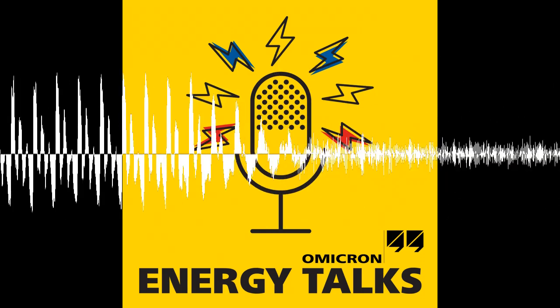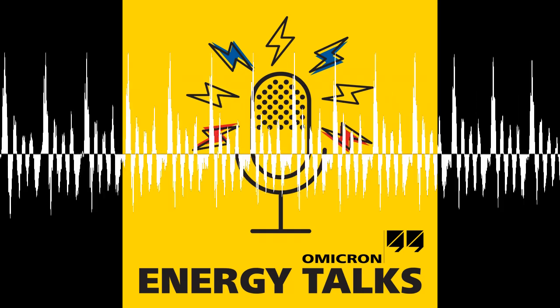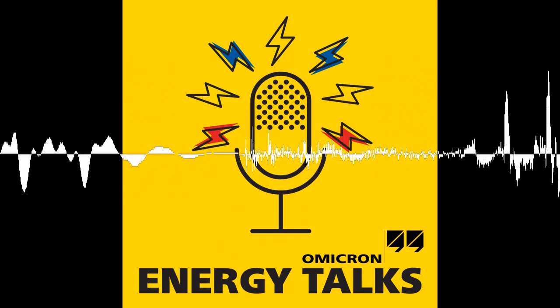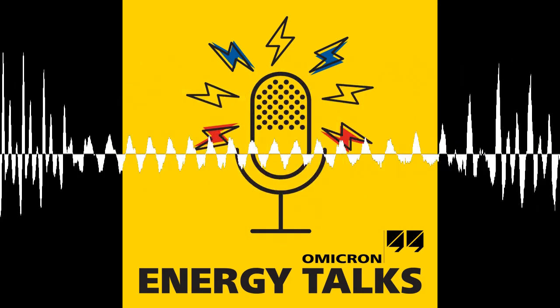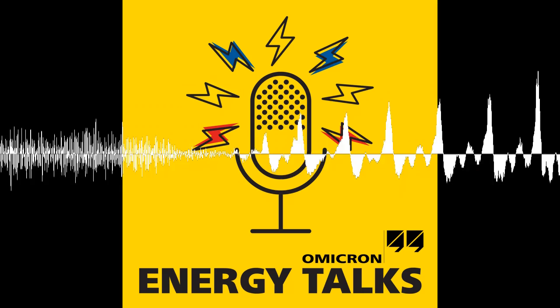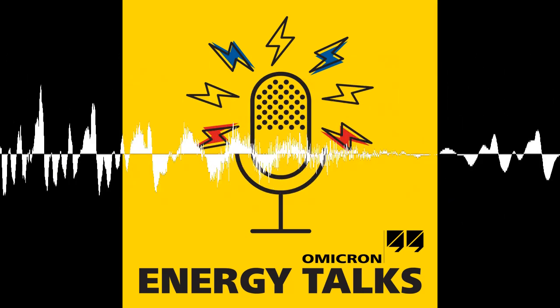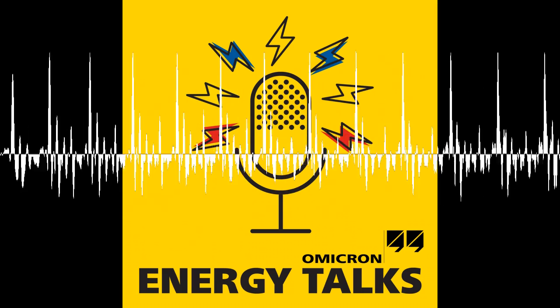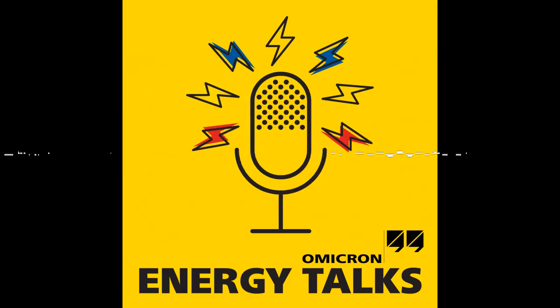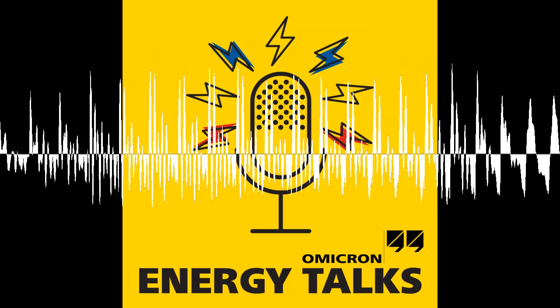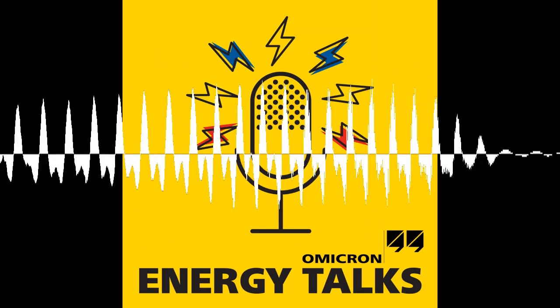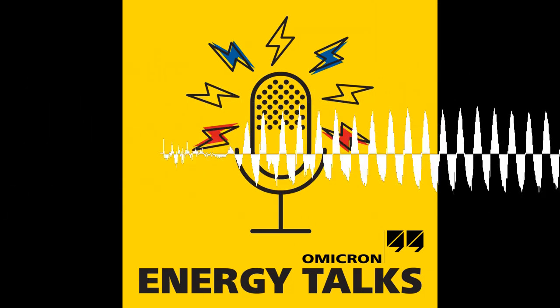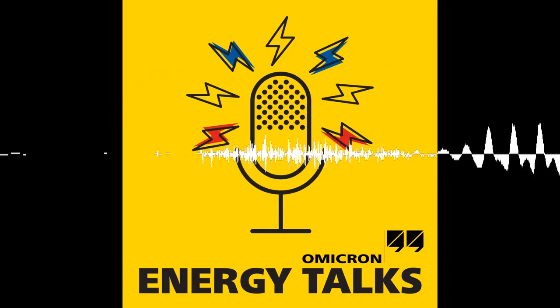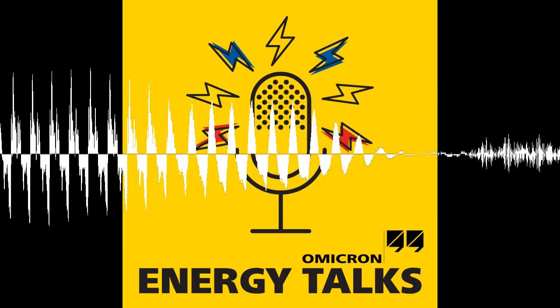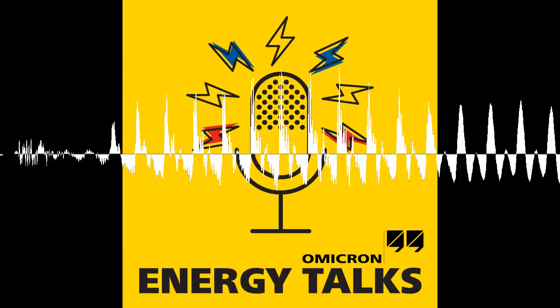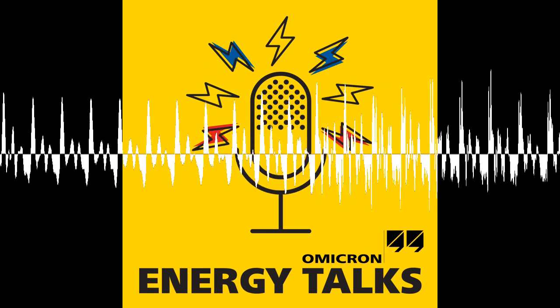Very good. Josef, let me ask you another question generally for our listeners who may not be as familiar with earthing or grounding testing. What are you really looking for? And when you have the data, what does it tell you about the substation equipment? What do you need to do as a result of those measurements to improve safety if you find irregular patterns? Okay, that's a good question. So actually, the ground impedance or the earth impedance of a substation needs to be below a certain limit to ensure safety. Usually, this impedance multiplied with the fault current gives you the ground potential rise in case of a fault. And this must be below a certain limit.